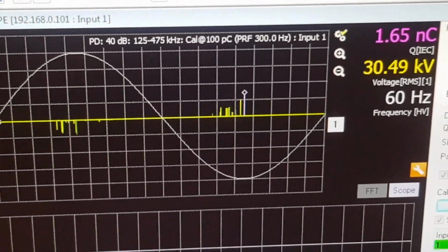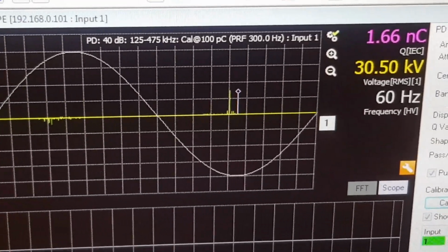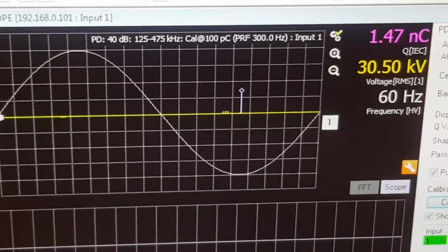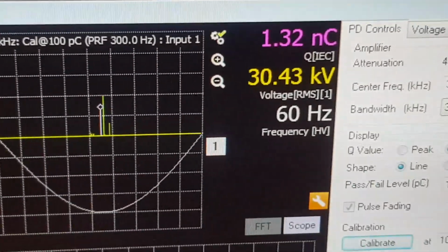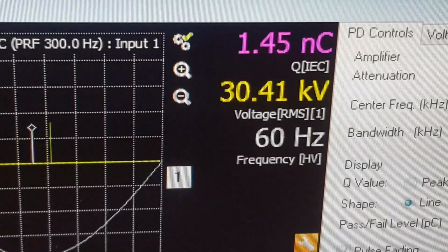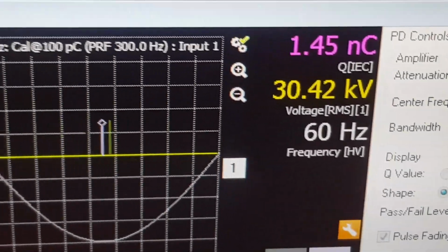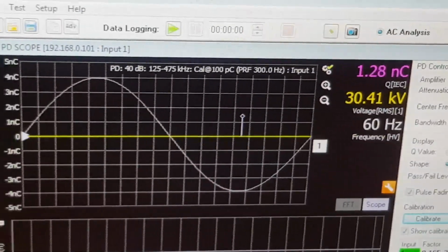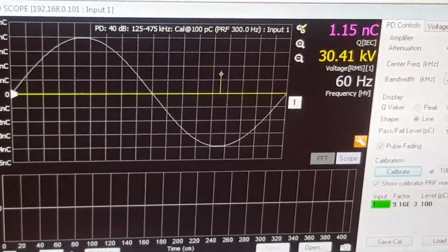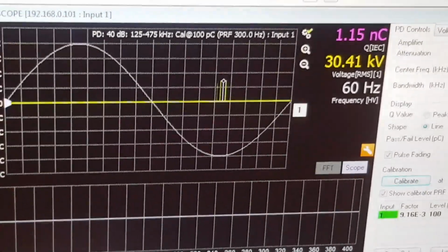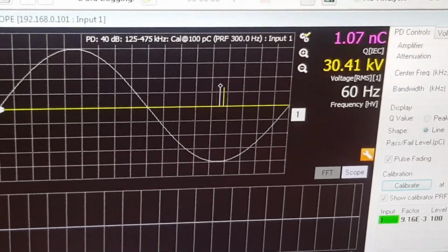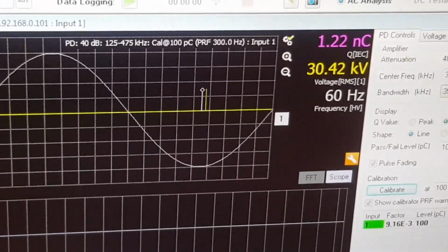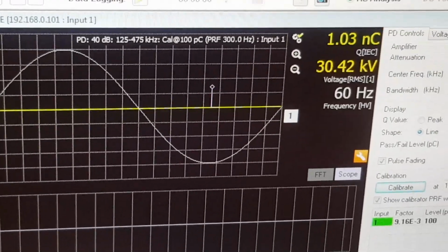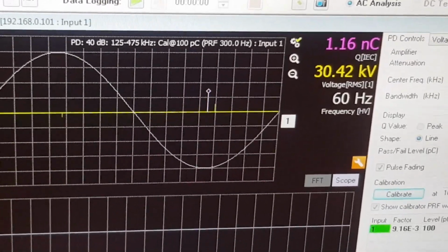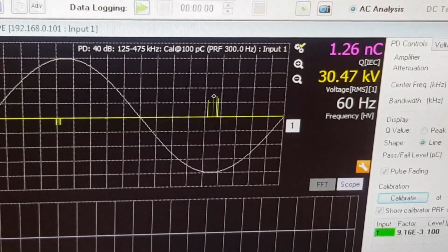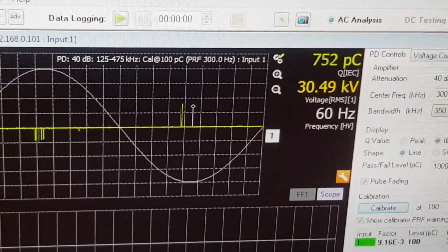Now when we applied 30 kilovolt to these two discs, and one of them is defective, you can see here the level of partial discharge is extremely high, 1.4, 1.5 nanocoulombs. The question is why we have such a high level of partial discharge. Now we will use different types of non-contact, non-intrusive sensors, and we will see these PD activities using these sensors. After that, I will explain what is happening and why we have this high level of partial discharge.